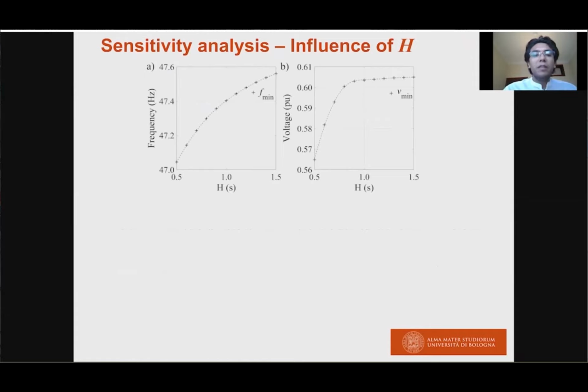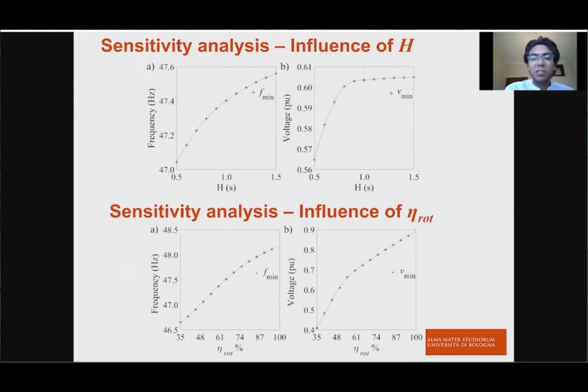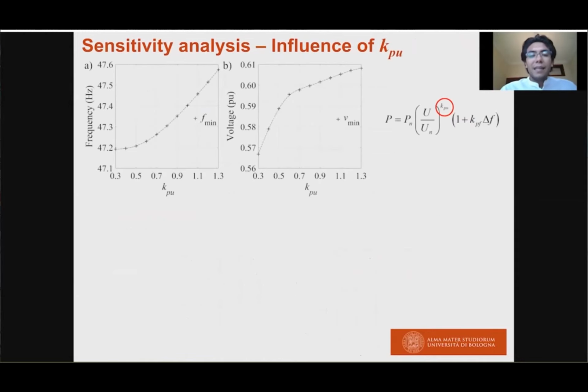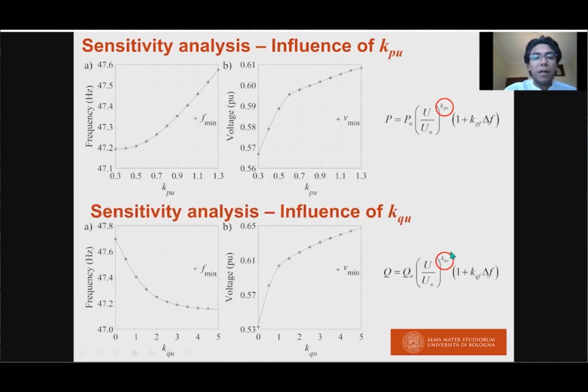In this slide, we report the influence of the inertia constant of induction motors and the influence of the percentage of rotating load. The increase of both, as you can see, leads to a minor frequency and voltage deviation. In this slide, we report the influence of the exponential parameters related to the voltage, as you can see. The increase of the active power parameter, KPU, leads to a minor frequency and voltage deviation, while the reactive power parameter, so KQ, leads to a greater frequency deviation but a minor voltage deviation.